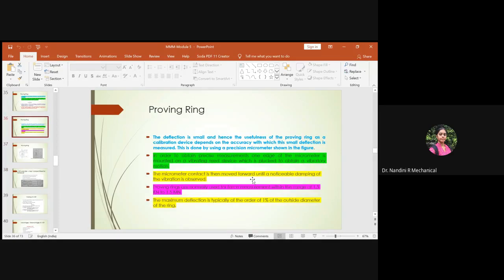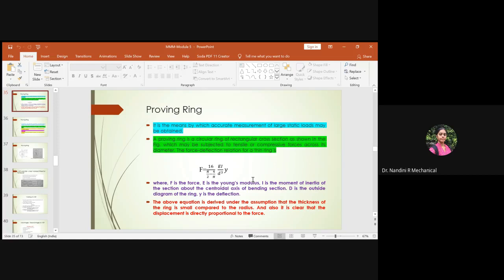The main thing to understand is that the proving ring is mainly used to measure static loads, so you get static characteristics. It is always associated with large values of static loads, so you can evaluate the static characteristics for large amounts of weight induced in a given material. When force is applied, deflection comes into picture.